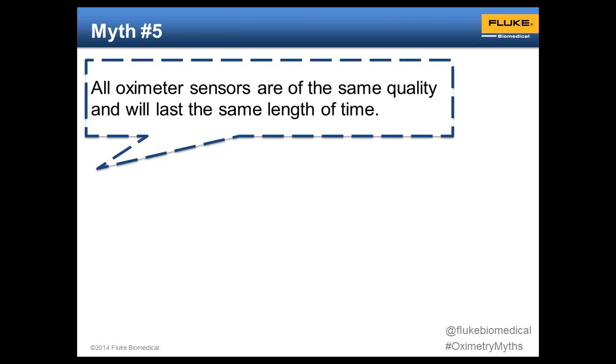Next myth: all oximeter sensors are the same quality and will last the same length of time. Every oximeter sensor is different. Between the manufacturers, they use different components, different R curves, and they assemble them in different places in the world with different quality control standards. That's why we recommend testing them annually, and we're going to get to that as well. But be mindful that each set from each manufacturer could last a different amount of time.